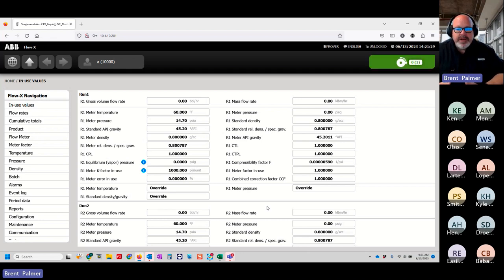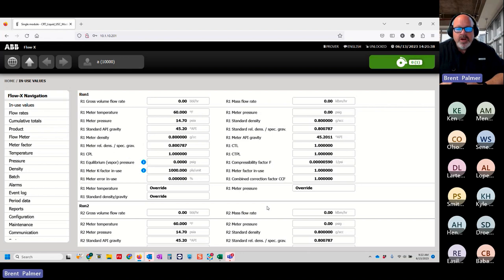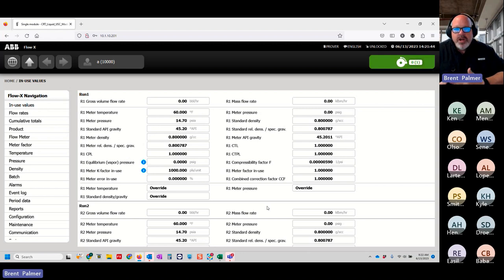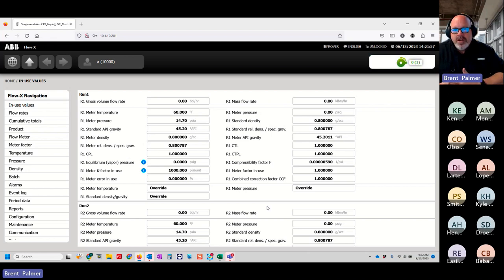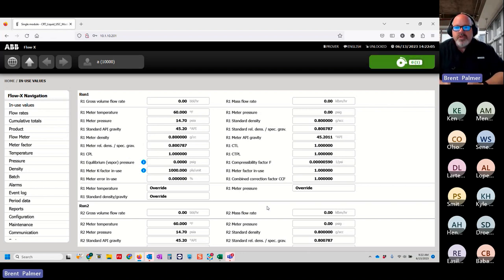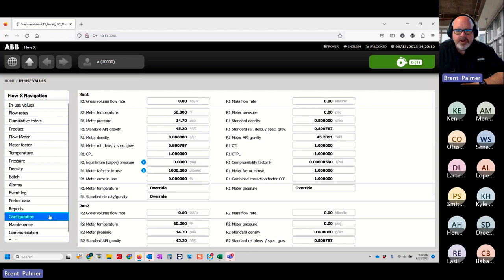To prove, I need to make sure I have physical pulses coming in. With the Flow X I can simulate pulses in maintenance mode by enabling pulse input, but I can't do that when trying to prove because at the FPGA level we actually need to see physical pulses coming in to start and stop counting. I need to see both the physical pulses and a digital input for the detector flag. The first thing to do in setting up the flow computer is tell it what kind of flow computer it is — I've logged in and I'll go to Configuration, then Overall Setup, then Main Settings.